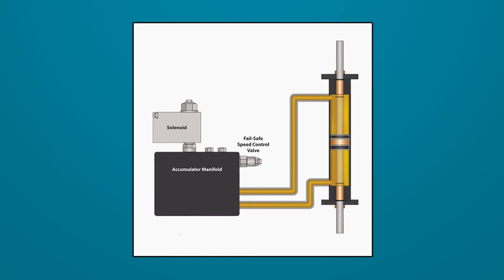As the surge is initiated, the solenoid valve is de-energized to allow accumulator pressure to drive the actuator cylinder to position. As the valve approaches the new target position, the solenoid valve is energized to stop the accumulator surge.